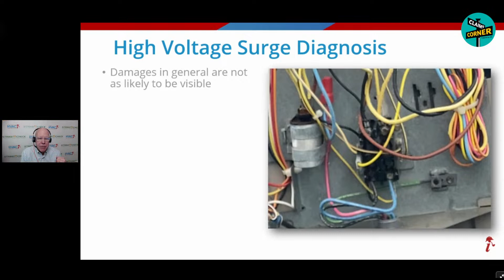This is a perfect example. This is a compressor. It looks relatively new. It's in good shape. It's being well maintained. And you wouldn't know as an adjuster with that picture whether it was damaged or not. Well, it turns out that one was damaged. All right. That one was affected by a surge event. So you definitely have to have that tested.